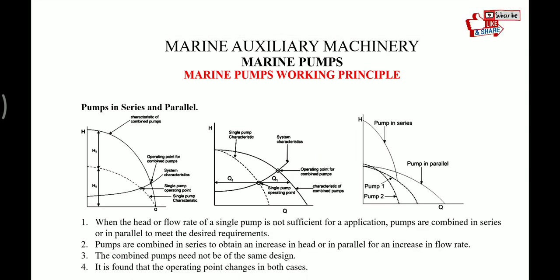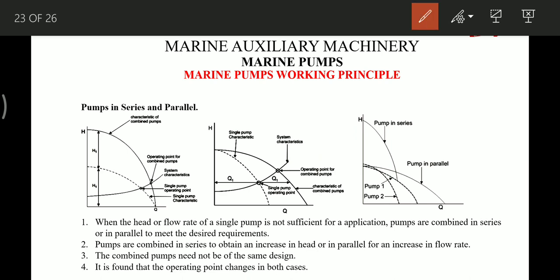Now, pumps operating in series and parallel. When a single pump operates, there is one operating point. When two identical pumps run in series, the combined characteristic curve shifts, giving a new — higher head — operating point. When two identical pumps run in parallel, the combined curve shifts to give a higher flow operating point, different from the single-pump case.